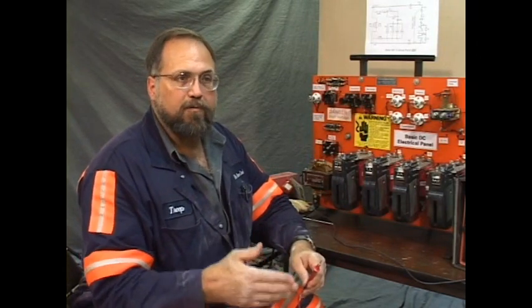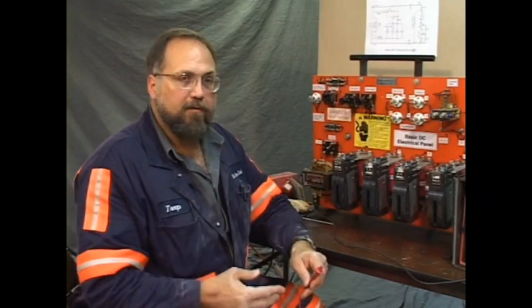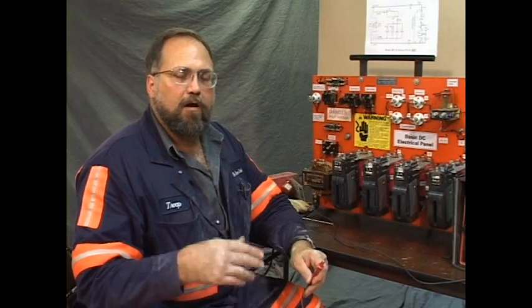Okay, fellas, we've illustrated 15 problems here, 15 different scenarios where you could find a fault. We've shown you the proper operation of the panel with power on it, and we've shown you the faulted panel, 15 different faults where you could press a button and note either the action or inaction of various parts of the panel and detect a problem. Now, those are all well and good, but to solve a problem in that fashion, you have to make deductions. You have to think and really truly have a keen grasp of exactly what's going on with the circuit.